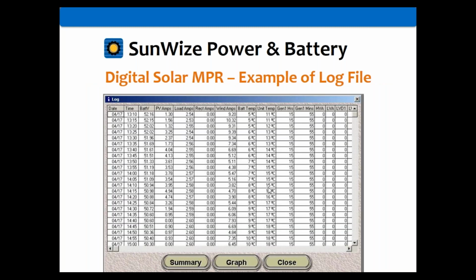This is logged data, logged in 15-minute intervals. I can see the date and time, battery voltage, array current, and load current at that time. It also tells me how many hours the generator's run — since this has advanced generator control, I know generator run time down to the minute, something you may not get from some other products.